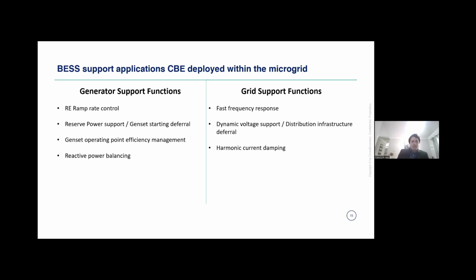Some of these will be well known, some of these are a bit more unique. So on the genset side, we implemented ramp rate control on the renewable facility. We implemented reserve power support, or rather genset starting deferral applications. We looked at optimizing the genset operation point and very critical reactive power balancing. On the grid support functions, we implemented a fast frequency response application on the battery. We applied a very novel approach to dynamic voltage support, which also allowed us to defer distribution infrastructure. And we applied a harmonic current damping application as well.